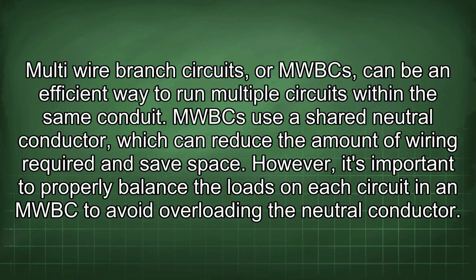Multi-wire branch circuits, or MWBCs, can be an efficient way to run multiple circuits within the same conduit. MWBCs use a shared neutral conductor, which can reduce the amount of wiring required and save space. However, it's important to properly balance the loads on each circuit in an MWBC to avoid overloading the neutral conductor.